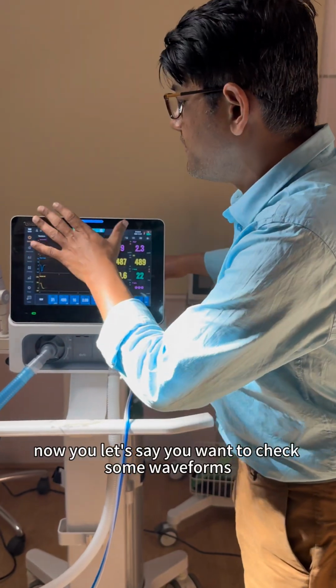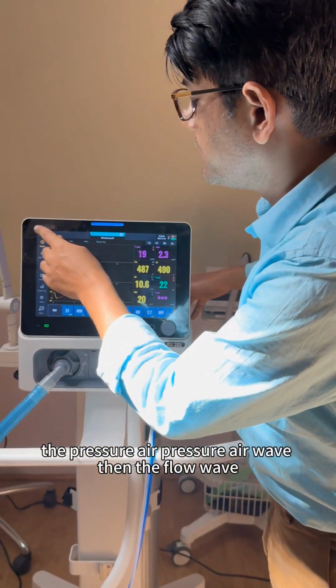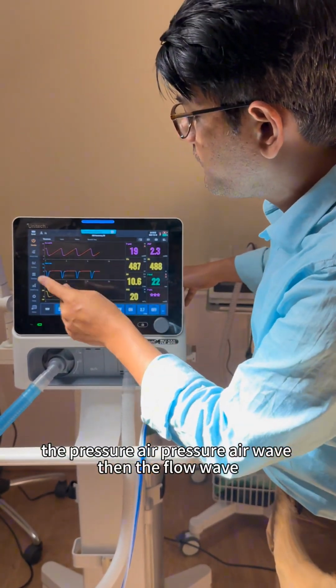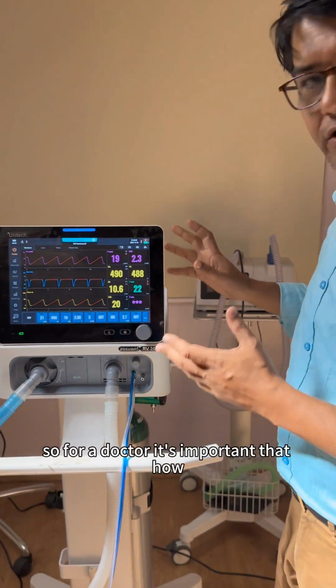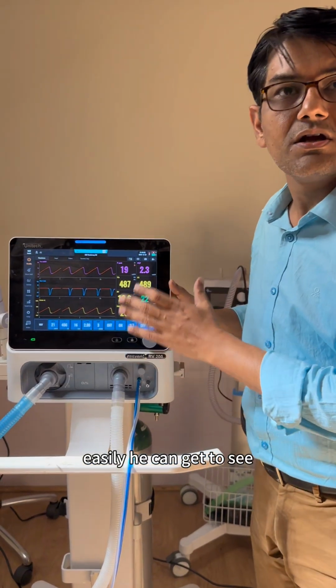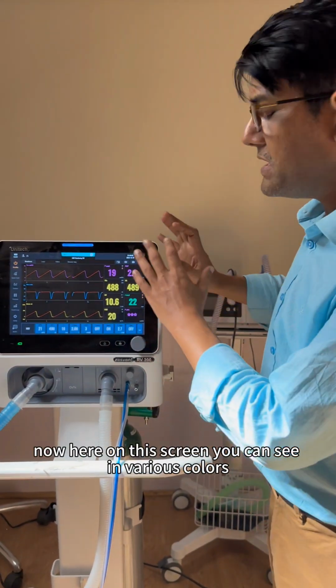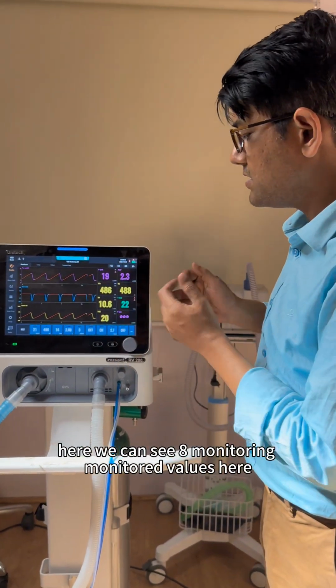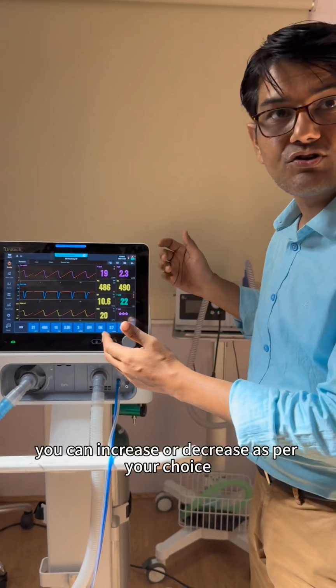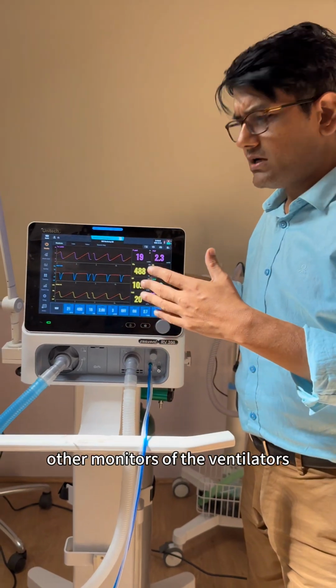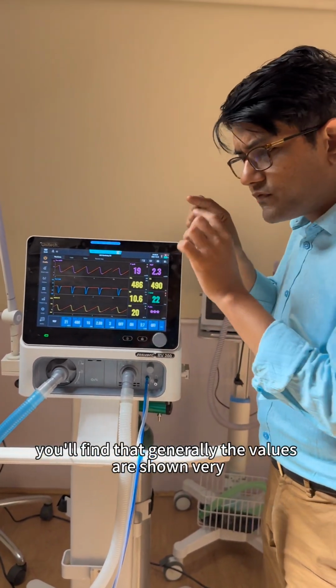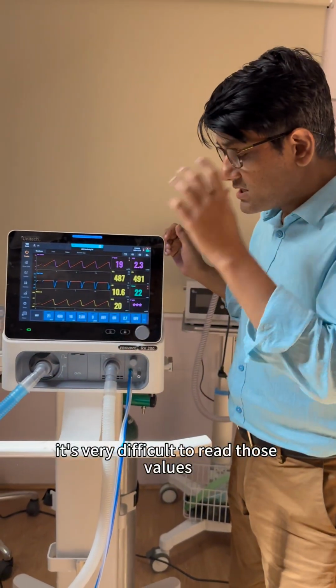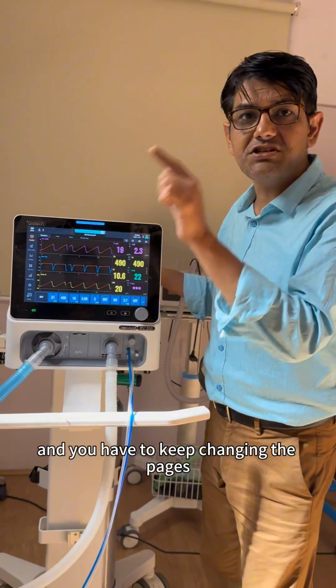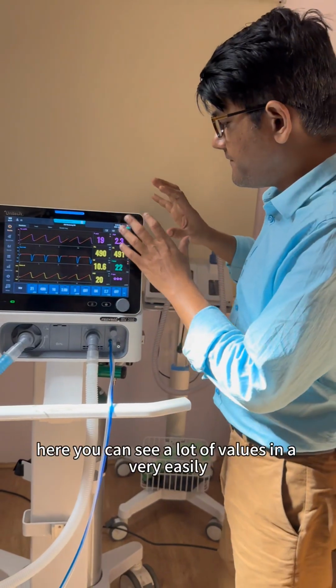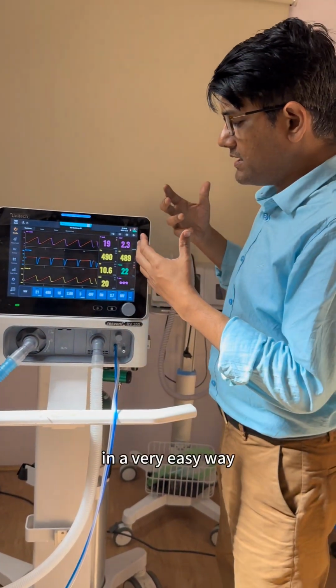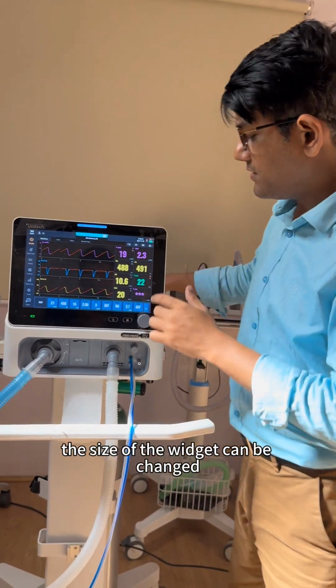Now let's say you want to check some waveforms. The waveforms are being shown here. The pressure wave, then the flow wave, the volume wave, and these are the values. So for a doctor, it's important how easily he can monitor the values. Now here on this screen you can see in various colors the large digits. Here we can see 8 monitored values. You can increase or decrease as per your choice as well. In other ventilator monitors, you will find that generally the values are shown very small. It's very difficult to read those values. Sometimes only 3 or 4 values are shown on the screen, and you have to keep changing the pages. Here you can see a lot of values in a very easy way. The colors can be changed, the size of the digit can be changed.